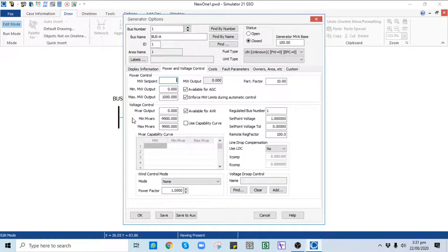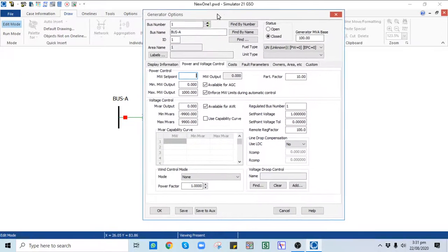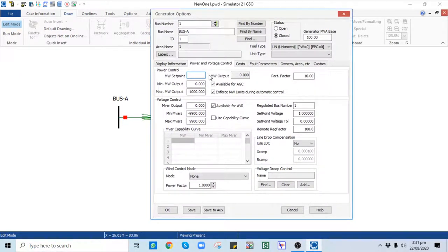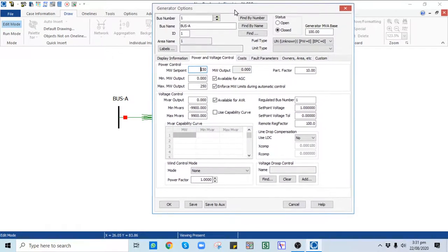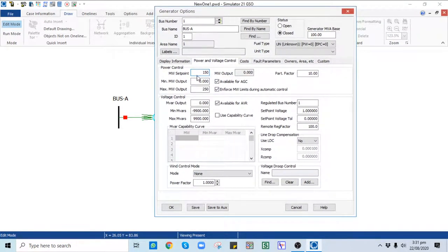Next is the generator. The generator is applied on a generator bus — we have already set that bus as the slack bus. You need to provide the megawatt input, like 150 MW, with a minimum of 0 MW and a maximum of 250 MW. These values can be calculated from the generator capability curves. We are not discussing generator modeling in detail here; that will be covered in upcoming lectures on thermal, hydel, solar, and wind generator modeling.